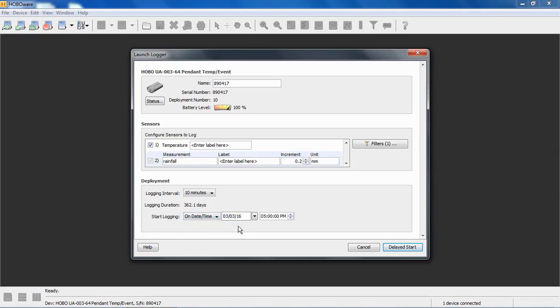We can also set the logger to start at a future time and date up to six months in advance. This is a great way to synchronize multiple loggers to the same starting time. So you can set all your loggers to start at the same time sometime in the future, take them out in the field, get them located, and leave them alone and they'll all start at the same time.